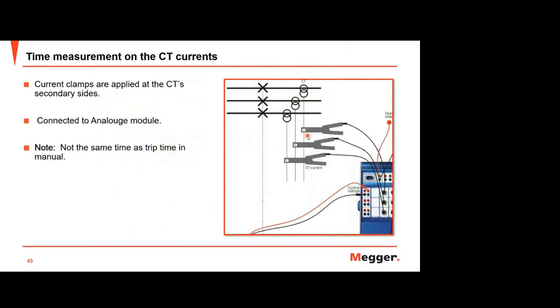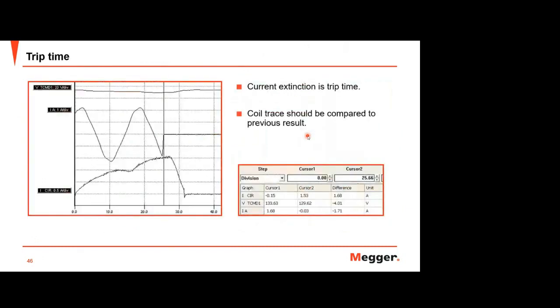From this measurement, you can detect the main contact timing. From here, you can see this is the coil current trace, and this is the load current. So we can decide this is the main contact operation, and from this coil current, we can define other parameters.